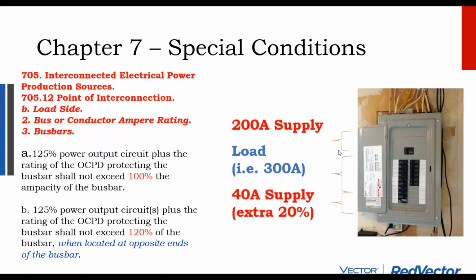And so code says we're going to allow you to connect solar to the very bottom of the bus bar, but you're only allowed to have that extra 20%, and that's it. So on a 200 amp service panel, you can have 200 amps from the utility and 40 amps of solar. You can have 180 amps from the utility and 60 amps of solar.